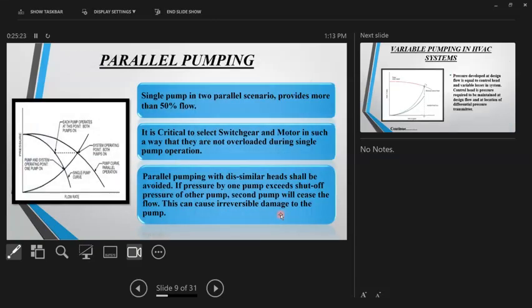A little bit about parallel pumping. Parallel pumping is again a reality of life. We never have a situation where we have only one chiller and one pump that feeds the whole system, correct? We always have standbys and multiple pumps. This is especially important where you have 30, 40, 50 pumps in parallel. Let's see what happens, starting with a simple scenario.